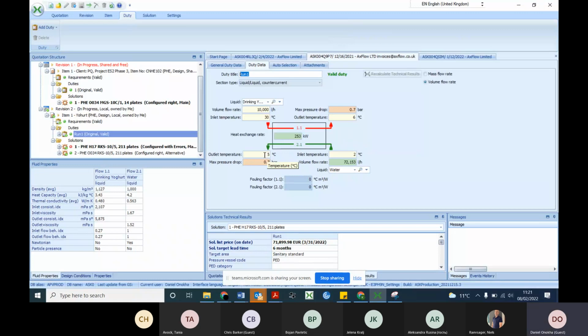I'm astonished to see that you're calculating on the outlet of your ice water. Why is that? I didn't know the flow rate of the water, so because of the 6 degrees, and I know it can't go over 6 degrees, I put 5 degrees here, and then calculated the power, the heat exchange rate, and the flow rate.